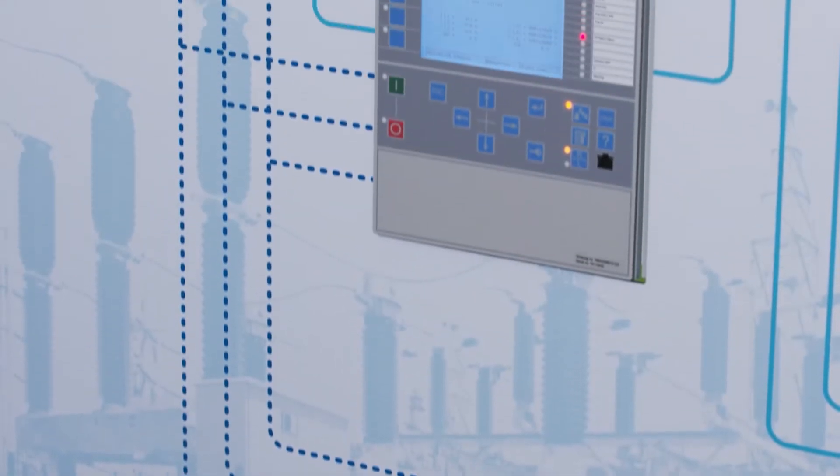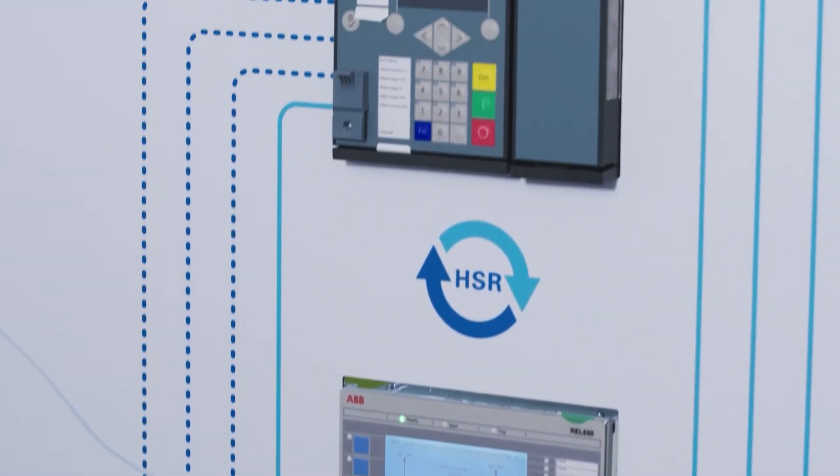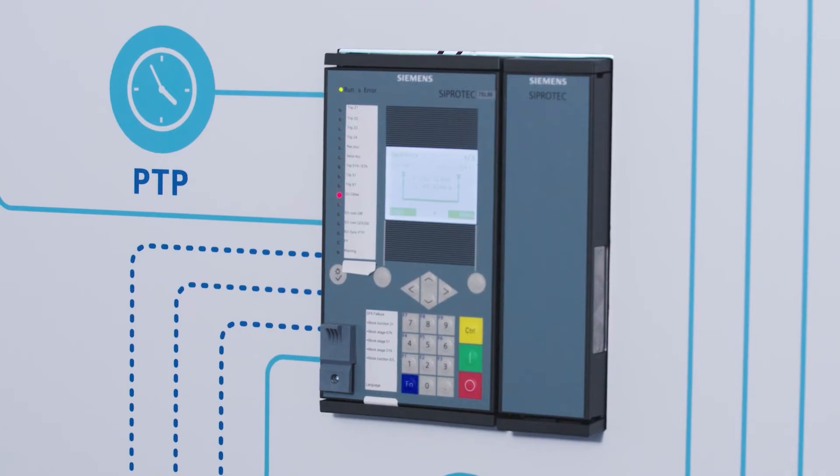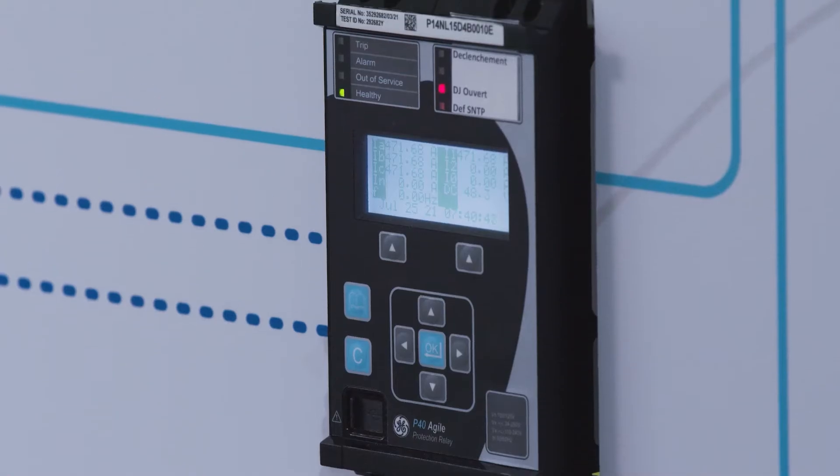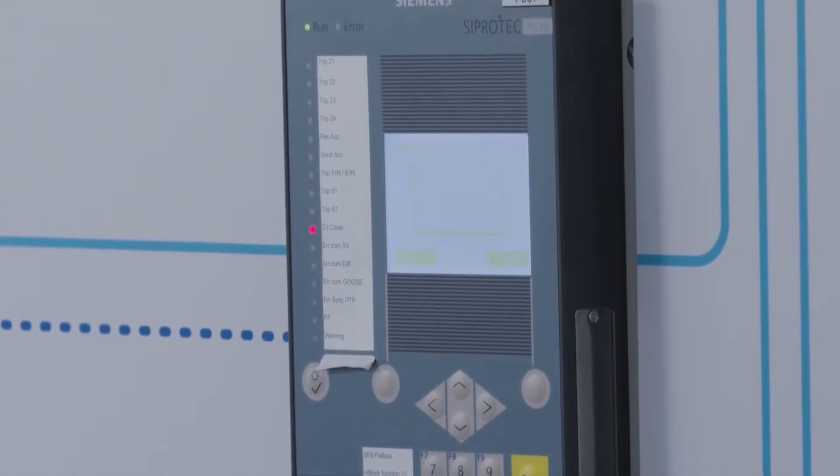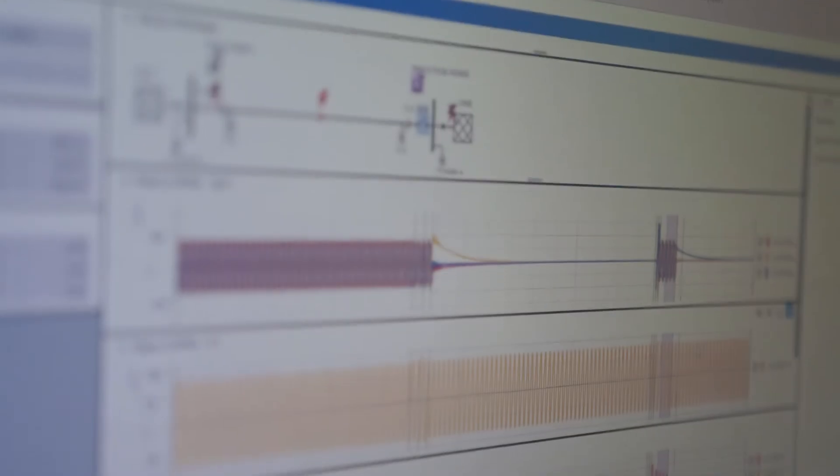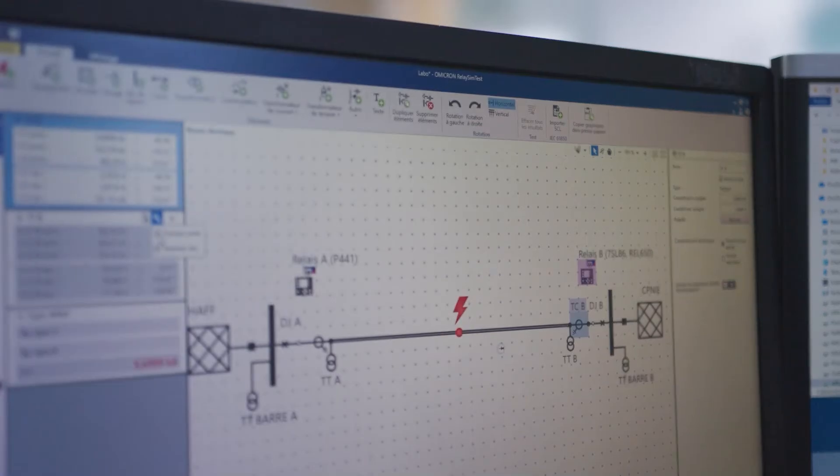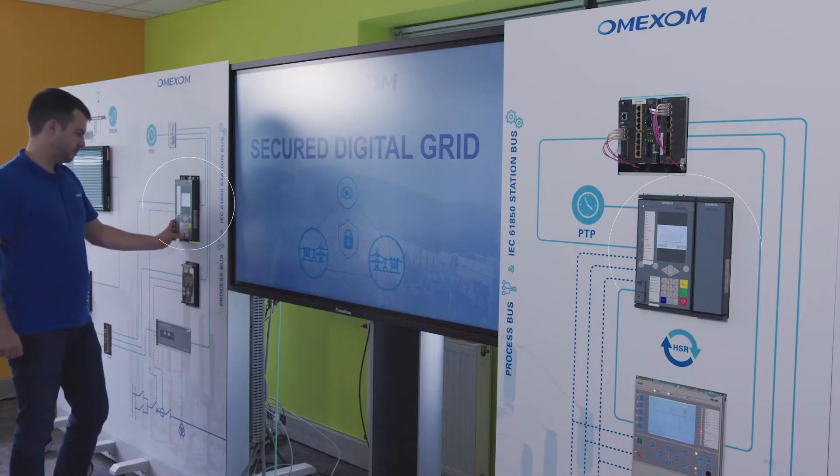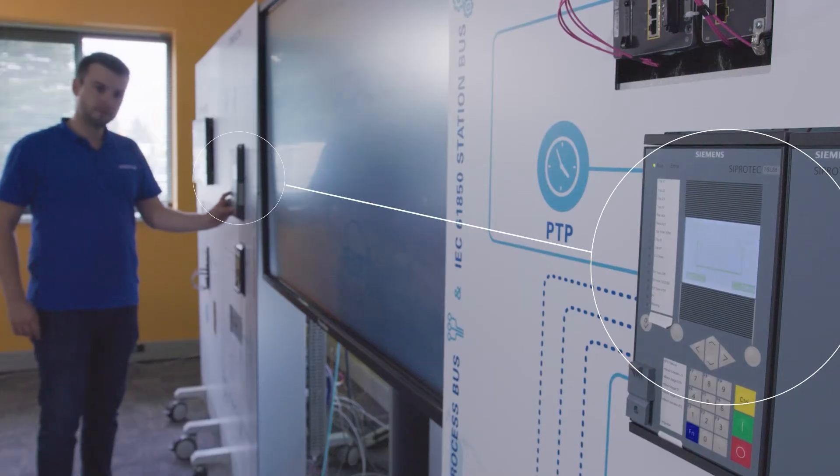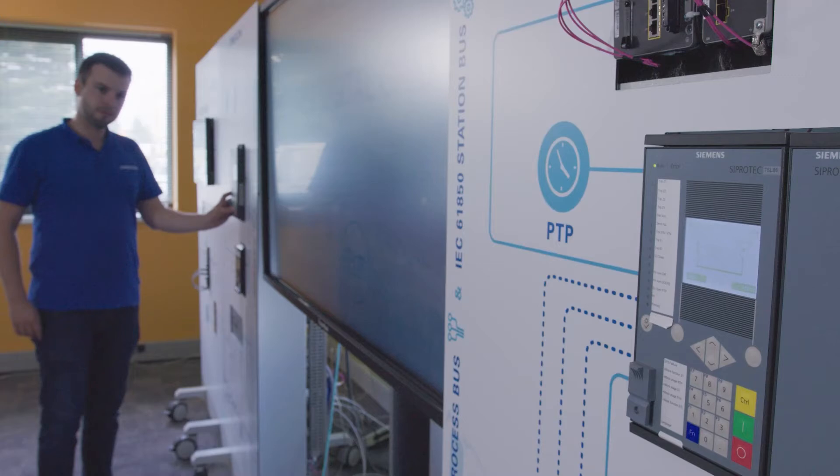On the Secured Digital Grid platform, IEC 61850 protections from ABB, GE, and Siemens have been integrated. Remote response and remote activation schemes have been implemented with IEC 61850 Goose communication. Two Siemens Differential protection devices also communicate using an Ethernet protocol through the network linking the two stations.